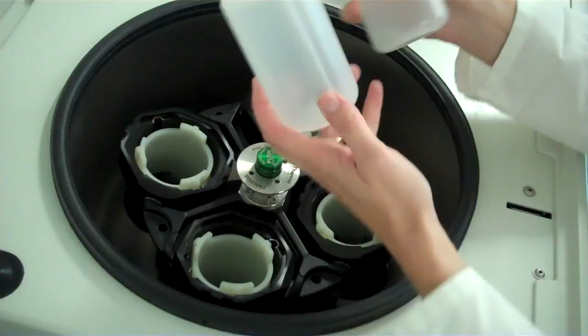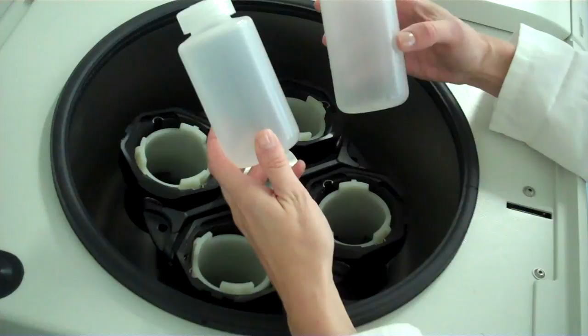All right, now whenever you place samples into a centrifuge, they must be balanced. That is, the two bottles that you put opposite each other in the centrifuge have to have the same weight. And so this weight needs to be with the caps. And the easiest way to do this is to simply weigh the bottles on an electronic balance and bring the bottle that has the least liquid or the least weight up to the weight of its counterpart.